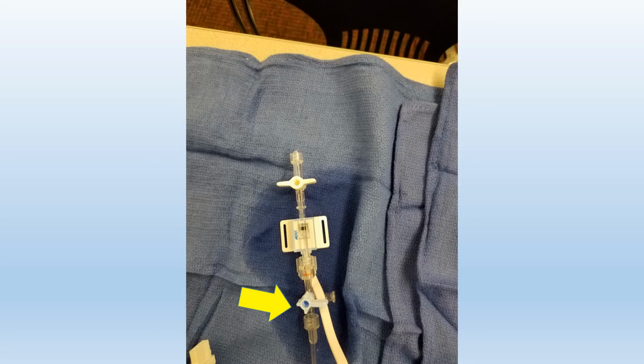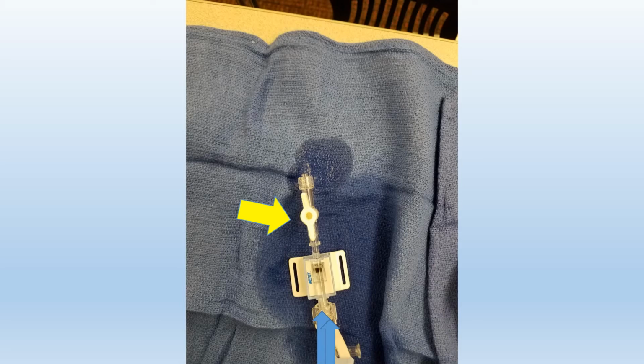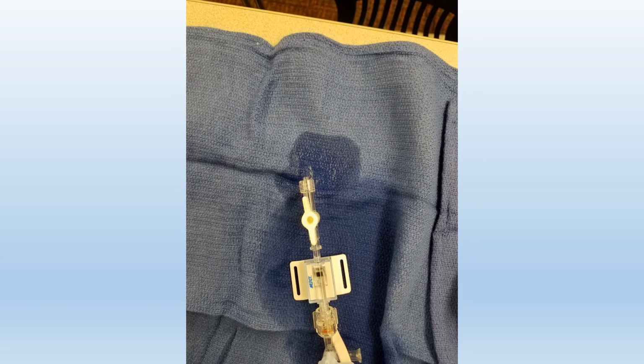We'll open up this stopcock right here, and what that does is it puts the fluid going through the transducer. What we want to do is hit right before the transducer a little bit so we can dislodge any of those micro bubbles that are hanging out, and push those through.